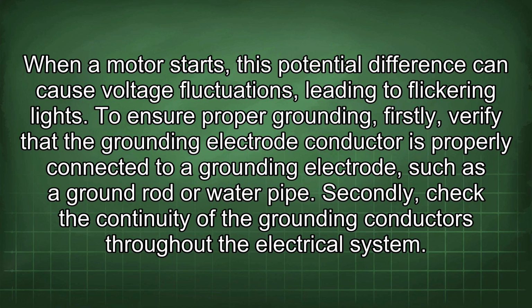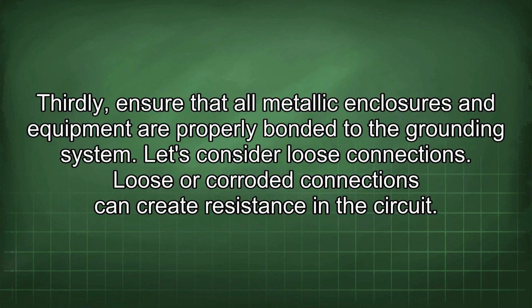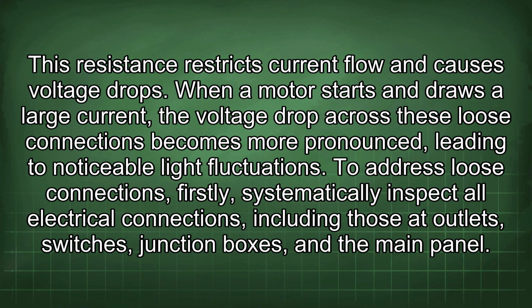Secondly, check the continuity of the grounding conductors throughout the electrical system. Thirdly, ensure that all metallic enclosures and equipment are properly bonded to the grounding system. Let's consider loose connections. Loose or corroded connections can create resistance in the circuit. This resistance restricts current flow and causes voltage drops.